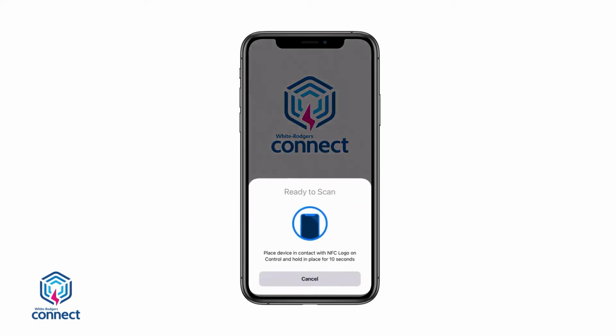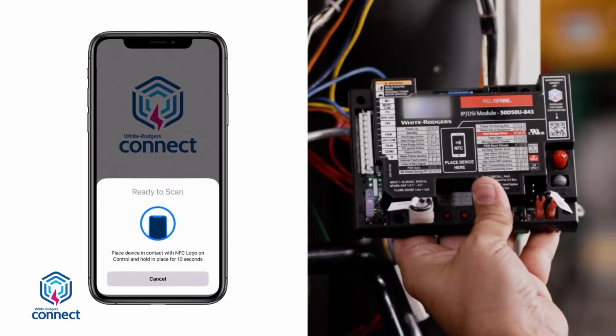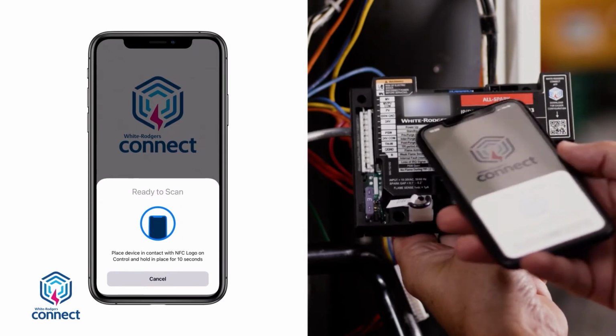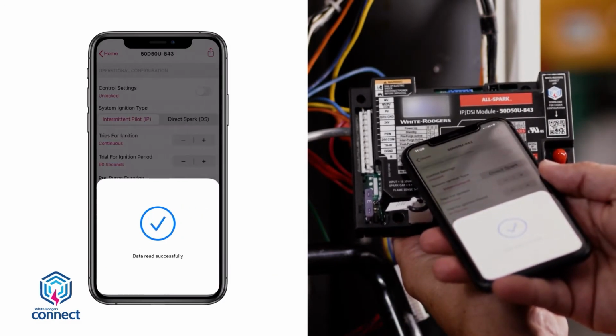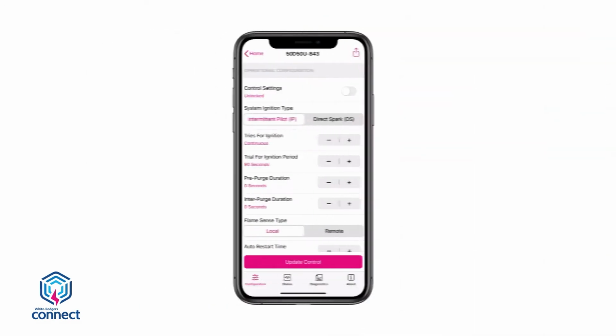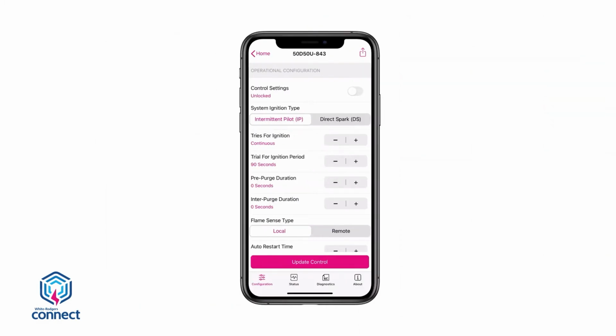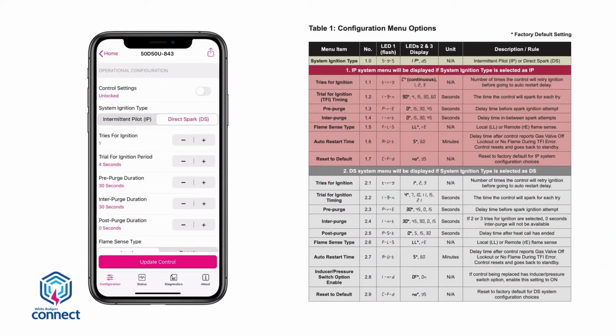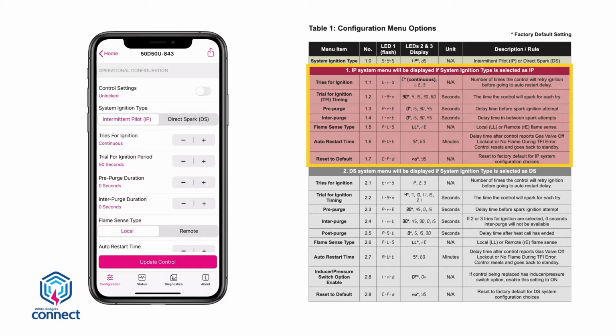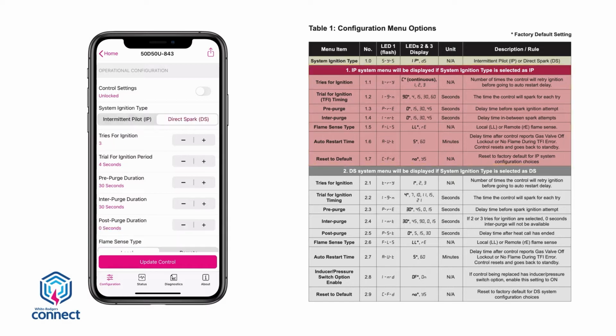The screen will show Ready to Scan. Place the mobile device in contact with the NFC logo on the module. A check mark will appear showing the connection was successful. The app will then display the 50D50U-843's settings configuration screen. First, choose whether the module being replaced is an intermittent pilot or a direct spark ignition system. Table 1 on page 3 of the installation instructions shows configuration options. It is divided into two sections. The first section shows configuration options for an intermittent pilot system, and the second section for a direct spark system.